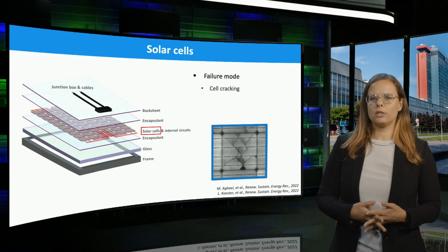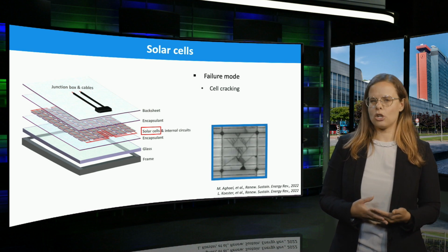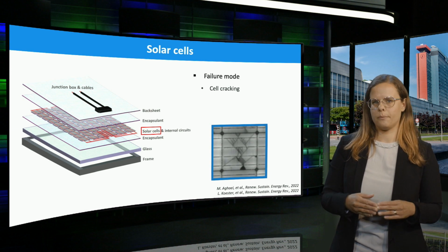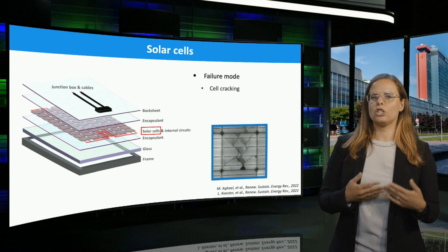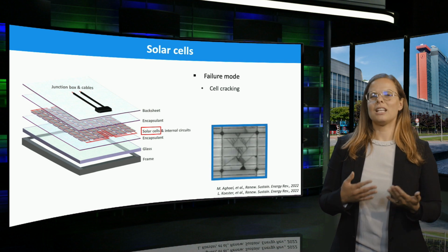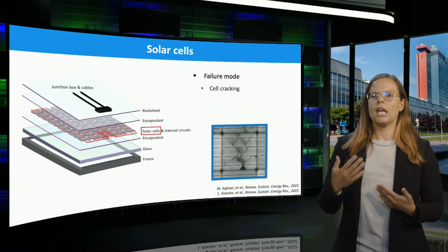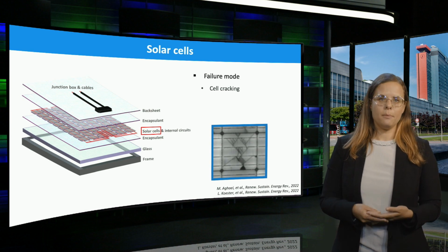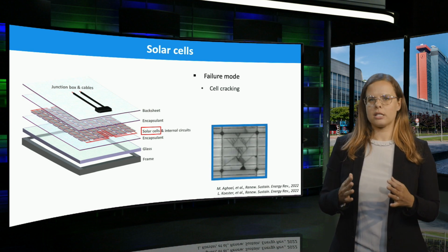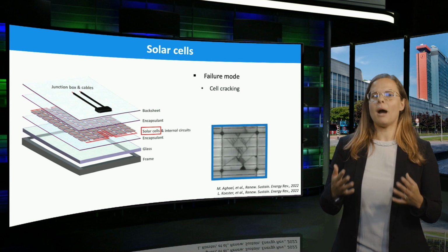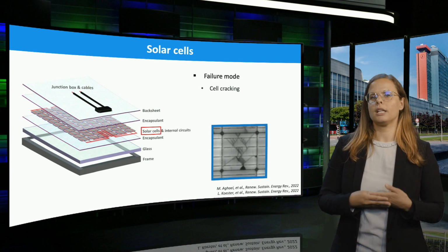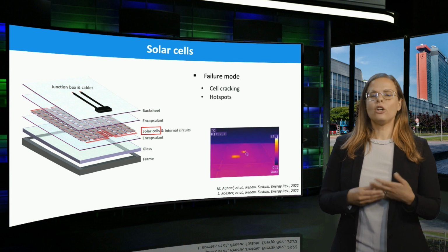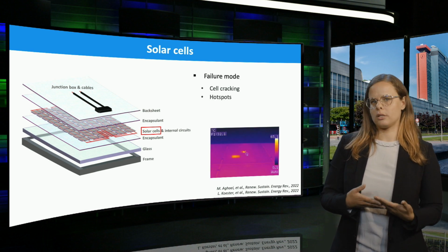On the bottom right, we show an EL image of a module with one cell cracked in multiple locations.